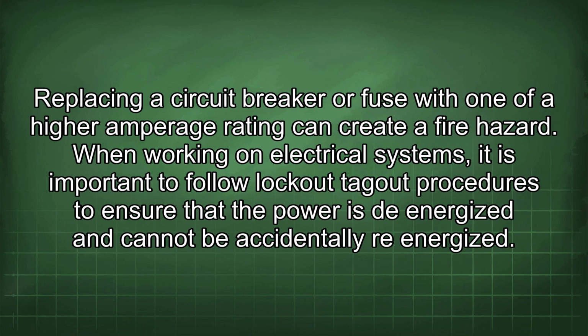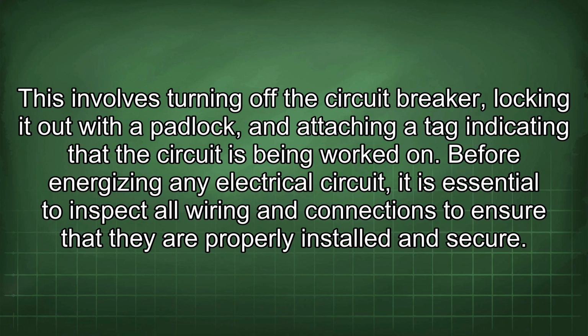When working on electrical systems, it is important to follow lockout-tagout procedures to ensure that the power is de-energized and cannot be accidentally re-energized. This involves turning off the circuit breaker, locking it out with a padlock, and attaching a tag indicating that the circuit is being worked on.